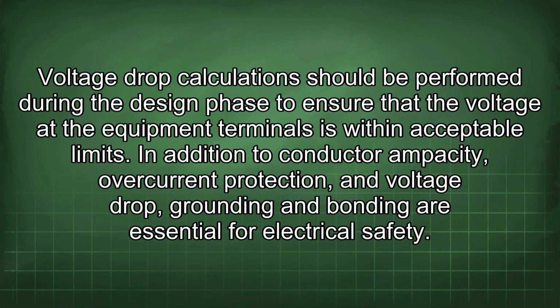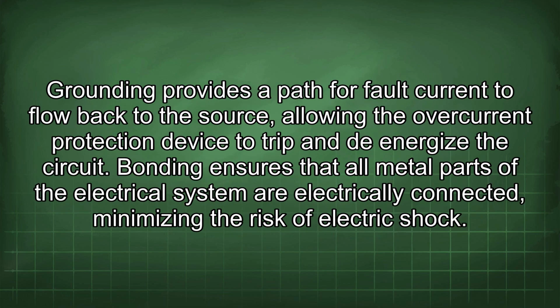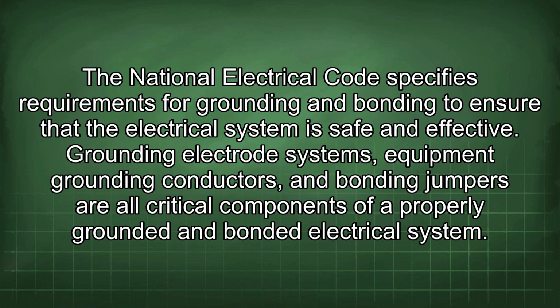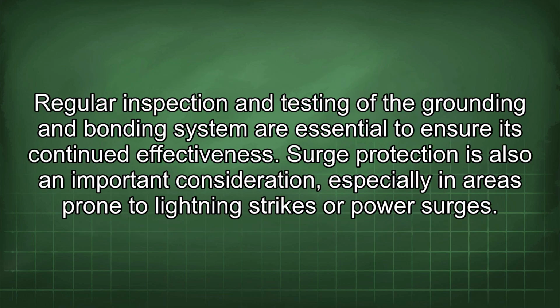Voltage drop calculation should be performed during the design phase to ensure that the voltage at the equipment terminals is within acceptable limits. In addition to conductor ampacity, overcurrent protection, and voltage drop, grounding and bonding are essential for electrical safety. Grounding provides a path for fault current to flow back to the source, allowing the overcurrent protection device to trip and de-energize the circuit. Bonding ensures that all metal parts of the electrical system are electrically connected, minimizing the risk of electric shock. The National Electrical Code specifies requirements for grounding and bonding to ensure that the electrical system is safe and effective. Grounding electrode systems, equipment grounding conductors, and bonding jumpers are all critical components of a properly grounded and bonded electrical system. Regular inspection and testing of the grounding and bonding system are essential to ensure its continued effectiveness.